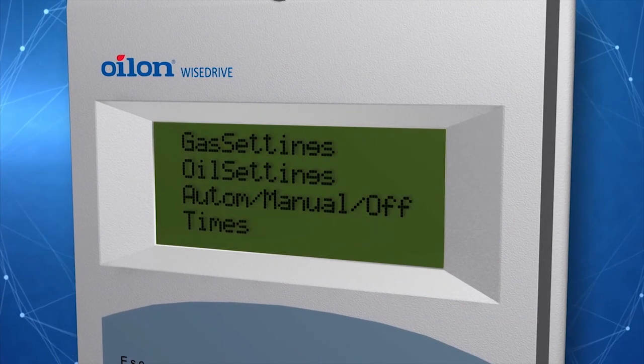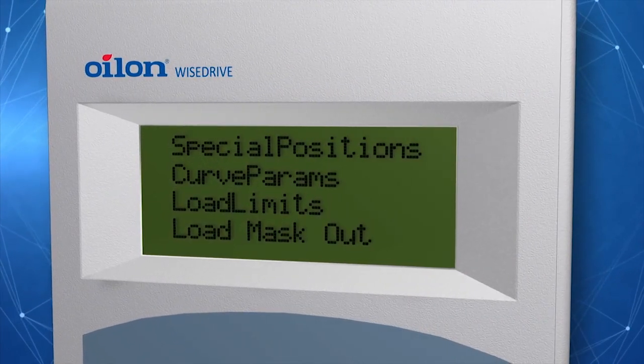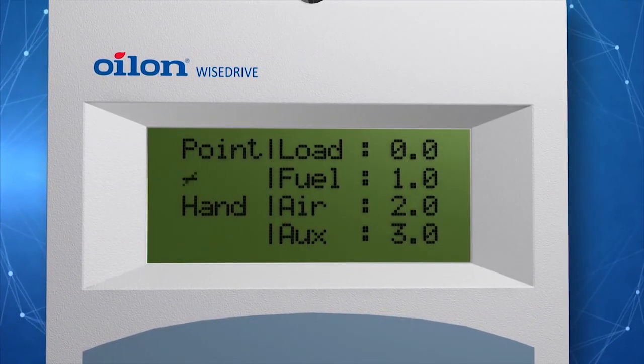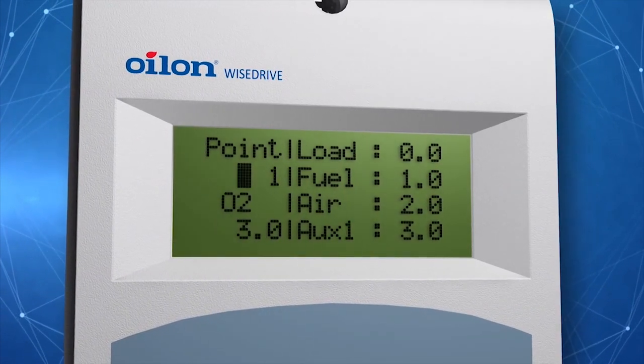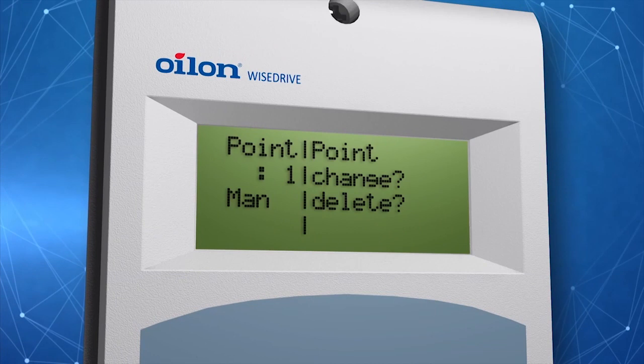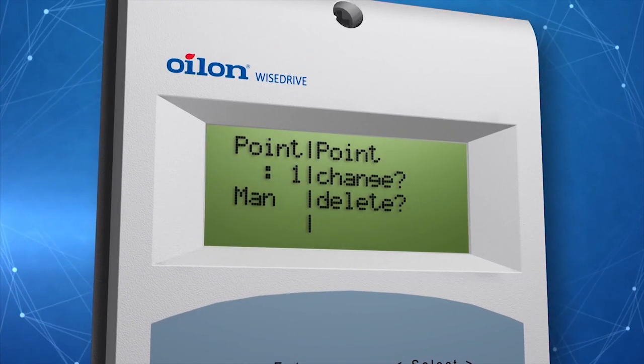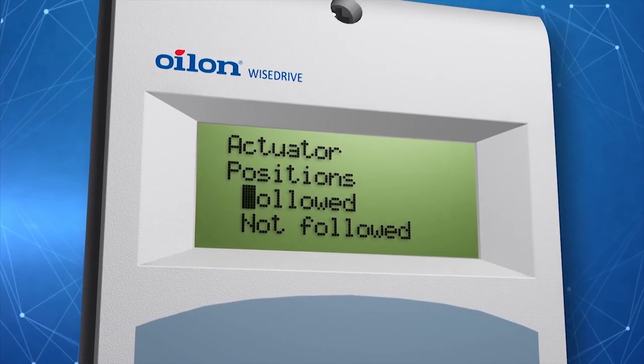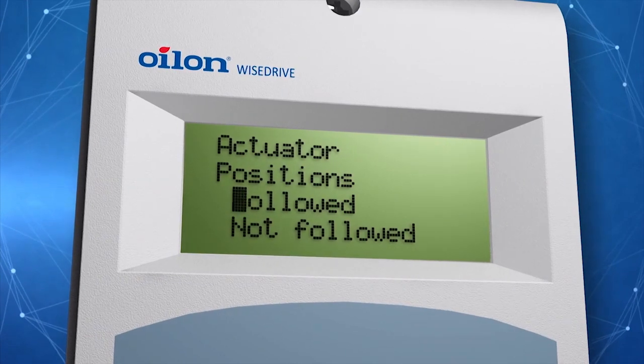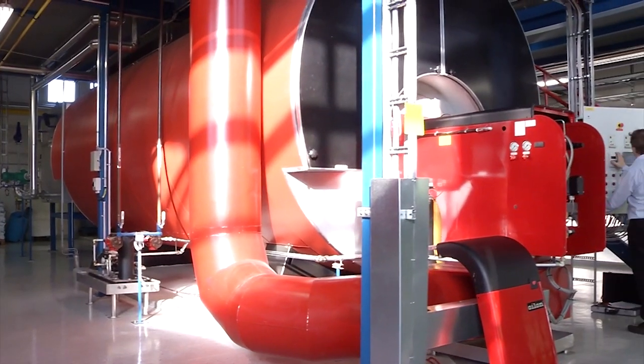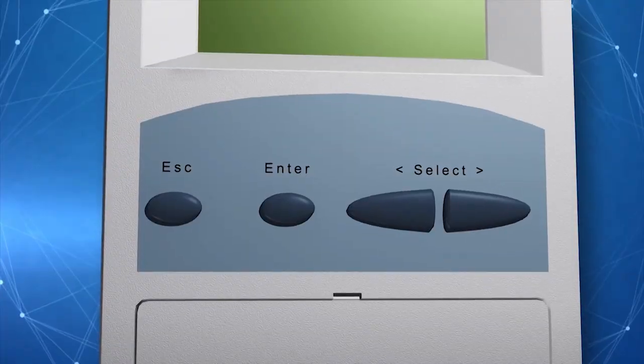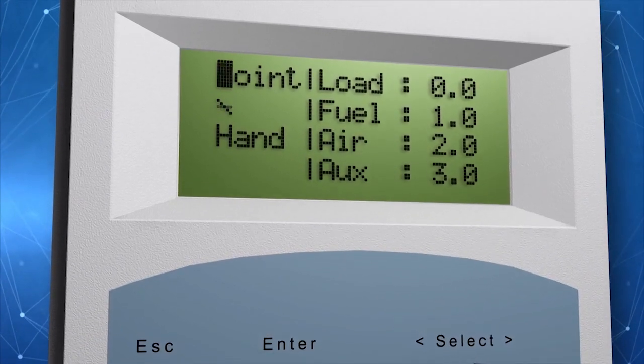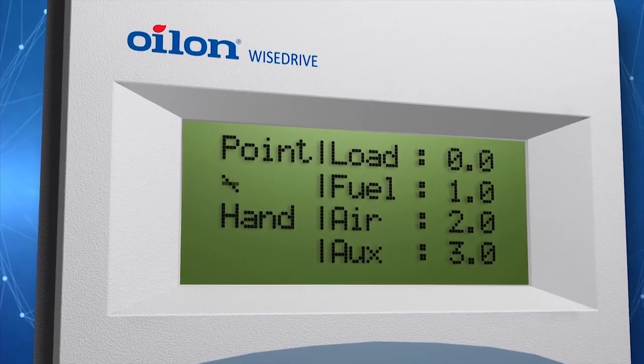Now you can set the curve points. Enter the submenu for the curve parameters. Press enter to set the first curve point, and press enter again to select change to modify the point data. When the system asks about the actuator position, choose followed. This means the actuators will follow the changes made to the point data in real time. The display shows current servo motor positions in degrees, frequency converter control, and capacity in percentages.